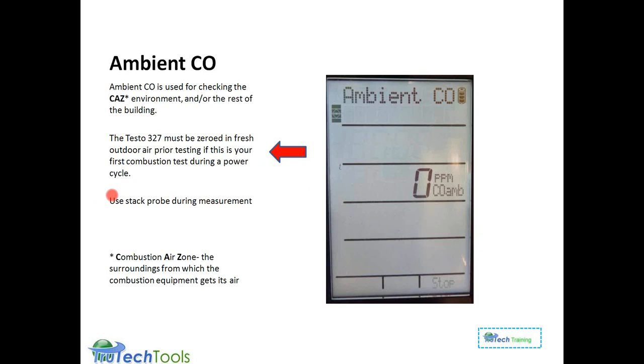We recommend using the stack probe during measurement just because you can get it into and around. You can hold it in the ambient air at a distance away from you, to make sure that when you're taking a measurement, you know where that measurement is coming from. If you notice over here on the left, there's a little icon with four bars on it that basically indicates that the pump is running. You may be in a situation where you can't hear the pump, and if that's the case, you can tell it has power to the pump by the fact that the four bars are moving upward on the side. When you press stop, it records the reading you've taken, and it labels it with the CO ambient parameter and measured in parts per million.